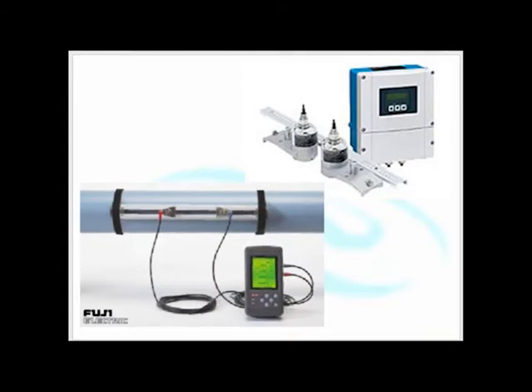They come in kits. The bottom one here is showing a kit form that you can strap onto the outside of the pipe. What I've done in the past is I had one of these kit form flow meters and I used it as my spare for all the flow meters in my factory. Because if anything went wrong, I could take this thing along, strap it onto the pipe, and then I'd take the 4 to 20 milliamp signal, strap it onto my ultrasonic, and I could be reading flow again within 15 minutes. And that then gave me a chance to do the really serious fault finding on whatever's gone wrong.